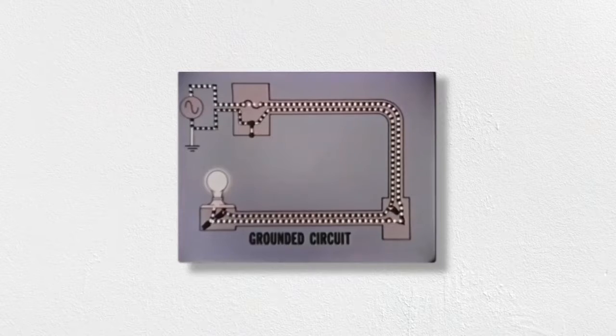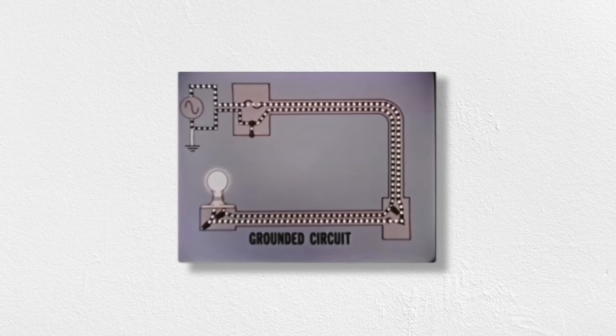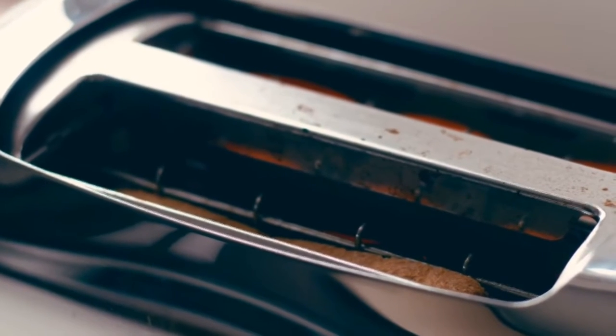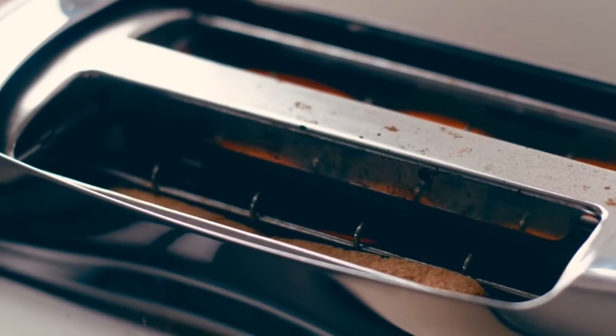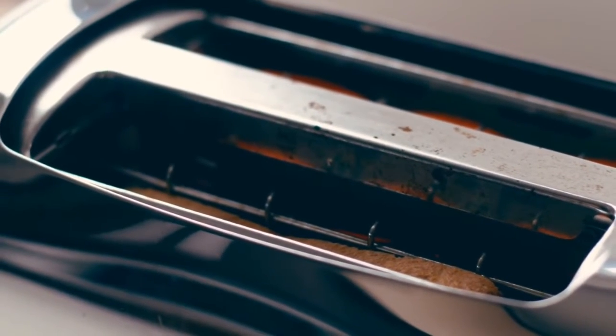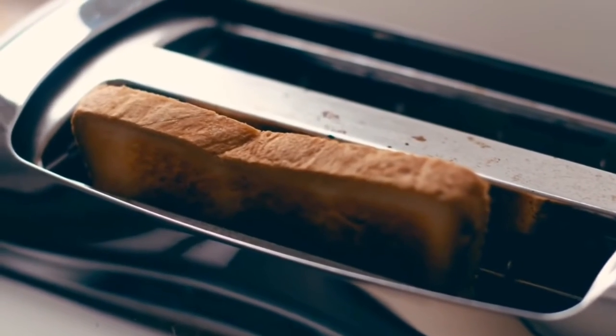Identifying and differentiating them can be a major challenge. The fundamentals of electrical devices can be boiled down pretty easily. Electrical current travels from a source through a series of components and back through a return path that's referenced to ground. There really isn't that much information that protective devices can use to identify problems. For example, there's very little difference between what's happening in your toaster and what happens when you take the live and neutral lines from a socket and short them together.